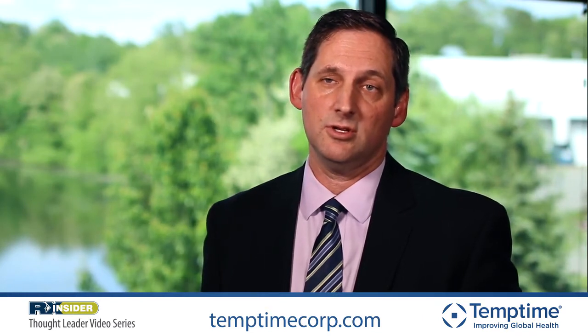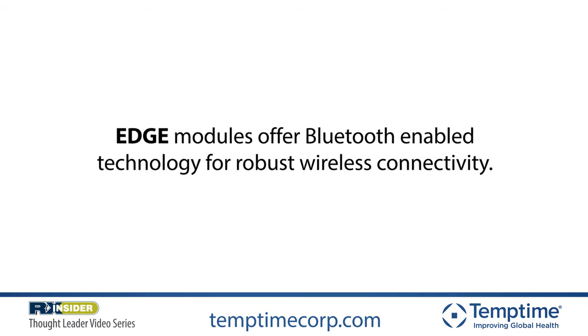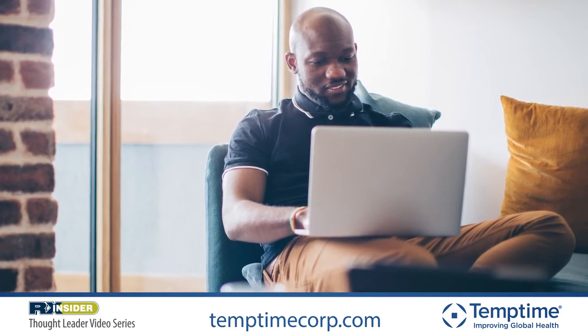The Edge devices are extremely easy to use. Setup takes under a minute with just a few steps, customized to your requirements. The S400 is pre-programmed with a very common application so you can just run with it. Installation only requires downloading the free mobile app onto your phone or tablet — no IT resources are required. On the W200 specifically, there is only one initial connection required for installation, and since they are wireless devices, you do not have to hook up to any power source or network connection. Data is automatically uploaded to the cloud in a 21 CFR Part 11 compliant manner, and access is secure for authorized users.